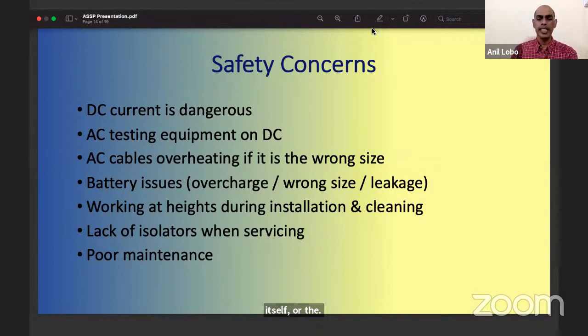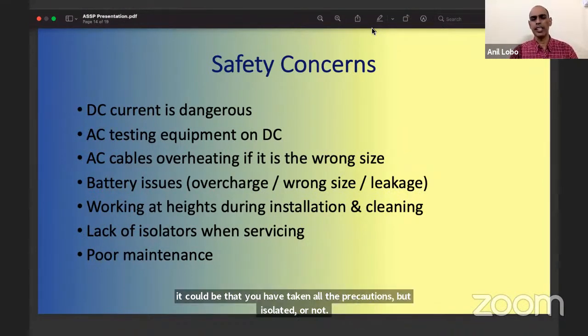If you do not have isolators, this becomes a challenge, especially when servicing the equipment. Why is this a challenge? A normal technician will think there is no sunlight, so he'll start working on the DC part of the cable, and the little moonlight that's out there is generating enough electricity to give him a shock. Sometimes it could be that you're at the wrong place at the wrong time, or you've taken all the precautions, but the isolators have not kicked in at the right time.